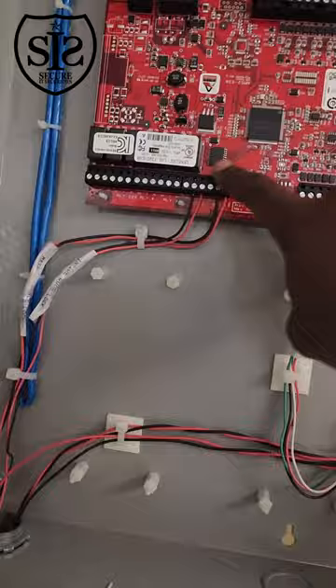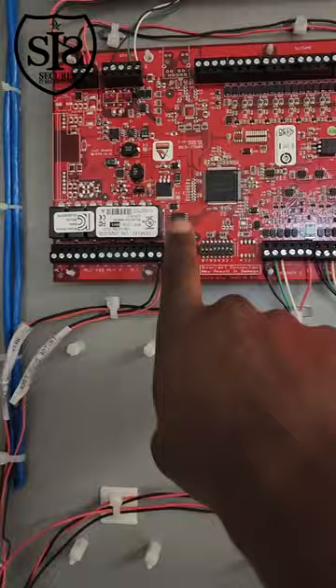The power supply from the relay up here goes into the input of the relay and the power supply, and these wires go straight to the door. When you get a valid card swipe, this relay will fire and in turn will fire this to unlock the lock so you can gain access inside the building.